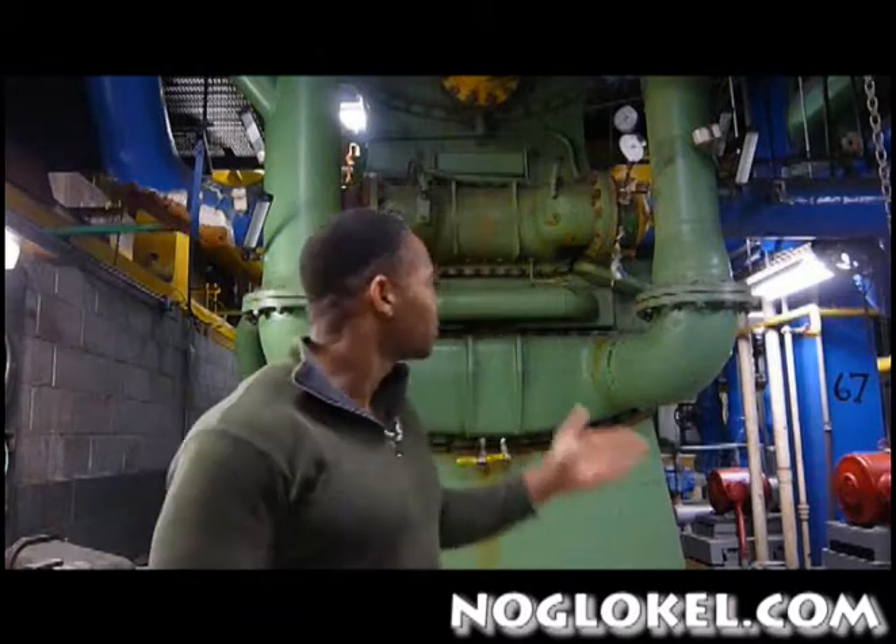What we're looking at is a steam driven absorber. The absorber is much like a mechanical chiller — it's designed to provide 45 degrees chill water cooling the desired space. The benefit of using an absorber as opposed to a mechanical chiller is that in some plants like this one, you may have steam available. This absorber runs off steam, about 15 pounds steam or so, so you're saving tremendously on electricity.